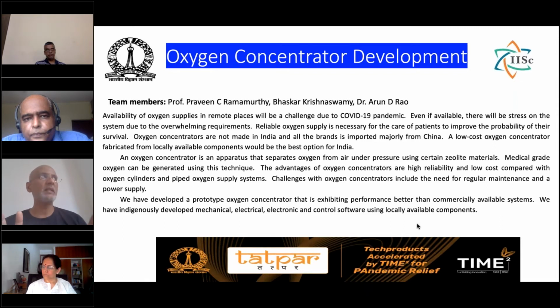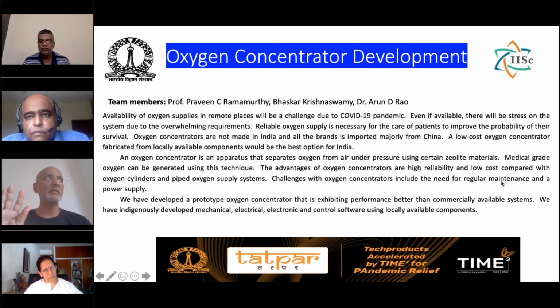The only difference is that the one Praveen will talk about can deliver somewhere between 5 and 10 liters per minute of oxygen. To put that number in perspective, the average human being breathes air at the rate of about 30 liters per minute—we are amazing machines ourselves. The oxygen generator that Professor Dasappa has put together is more of an industrial scale, and it can go up to maybe 50 liters per minute. So Praveen's concentrator is about 5 to 10 liters per minute—that's what he's calling the concentrator—and the oxygen generator can deliver up to 50 liters per minute. The principle remains the same.